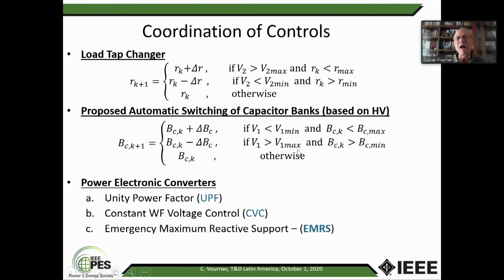If I have voltage above a certain limit, in this case something like 1.1 per unit, then I disconnect one capacitor bank. If it is within this min and max, this wide deadband, which is much wider than the deadband of the distribution side, which is plus or minus 1%, something like that, then if it is inside the deadband, or if I have switched on or off all the capacitance, then I do nothing.